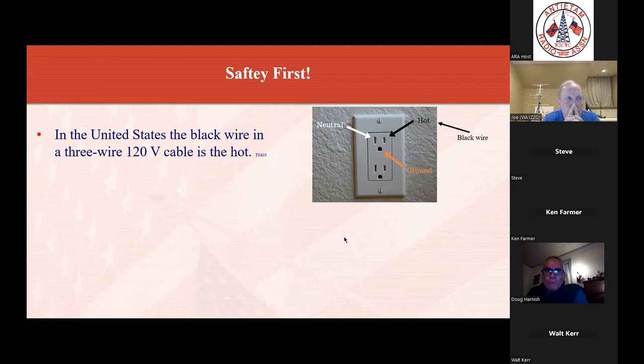But in the electric code, if you have an external ground rod, you got to have that bonded to the main ground by your electric panel. That's part of the electric code. And there's a reason for that also, because if you get a nearby lightning stroke, you can end up with the two grounds at different voltages and mess your equipment up. So yes, use a ground rod outside. That's more for the radiating part. The green wire ground is for safety, but you always connect the electric panel ground to your ground rod. So thank you. Okay, excellent point there. Thank you, Steve.